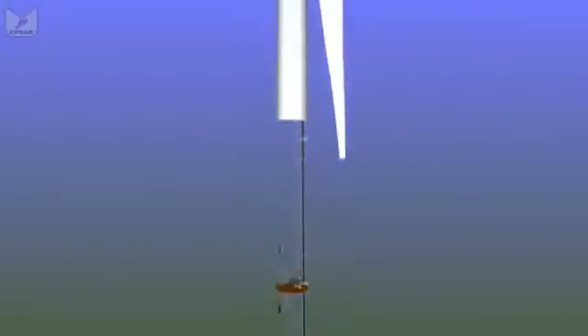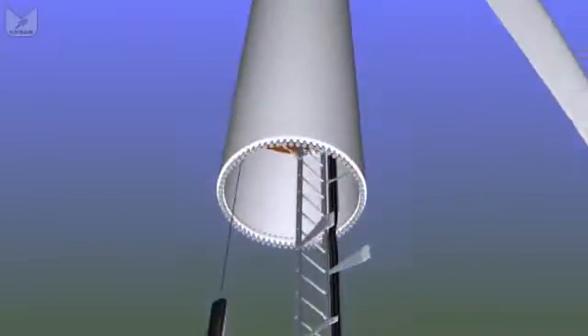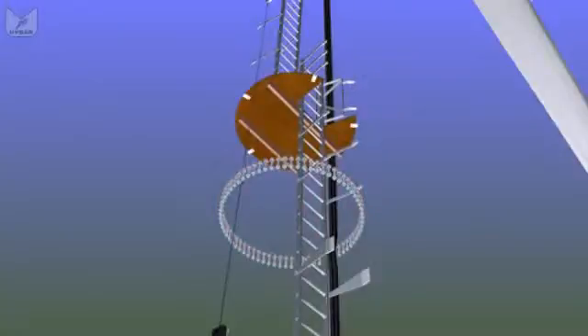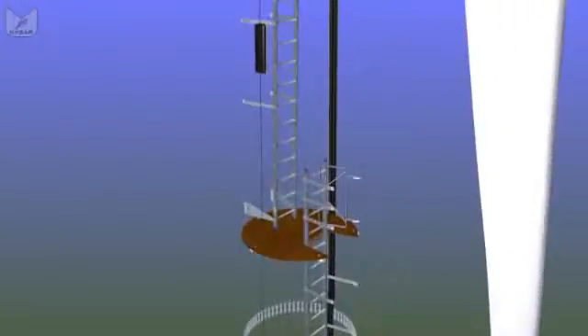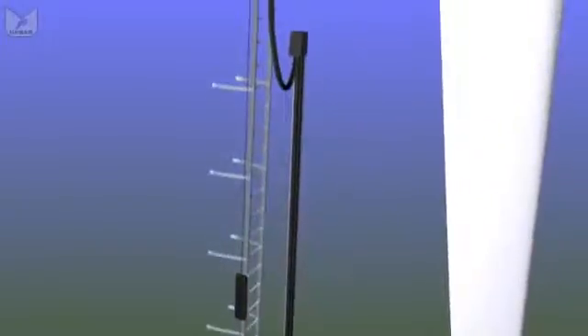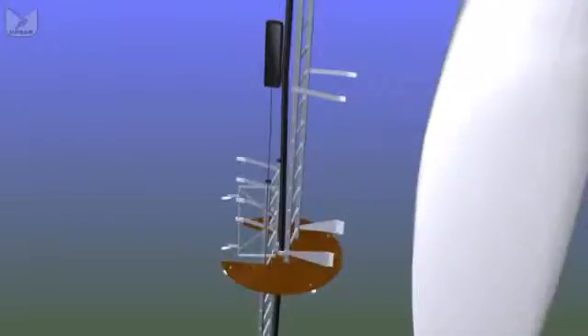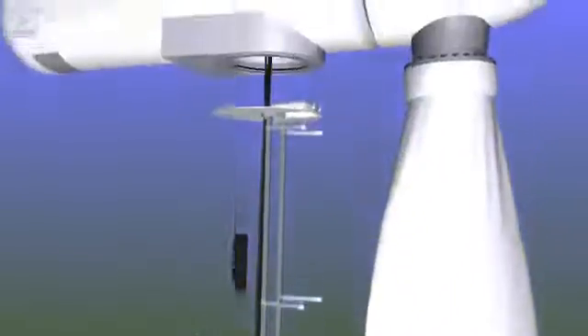The main cable goes up the wall of the tower, dodging past any intermediate junctions. Obviously the towers can't be delivered in a single 40 meter long section - they come in 20 meter sections bolted together. As we move higher through the platforms they're getting slowly narrower so the ladders are getting closer together. Eventually the main cables stop being attached to the wall and they hang freely in the center of the tower so they can twist as the nacelle rotates to face the wind. If they twist too many times the nacelle will spin itself around to remove the twists.